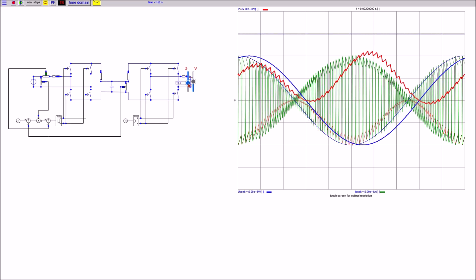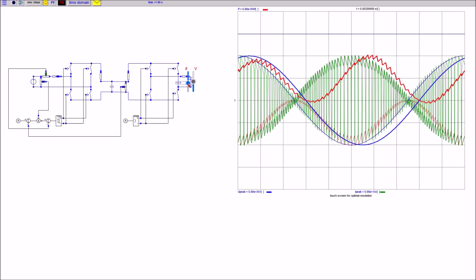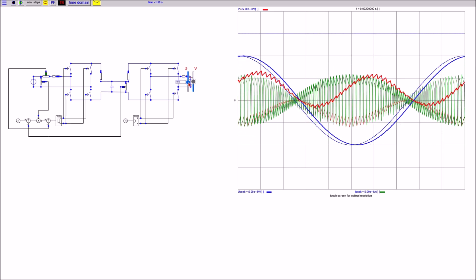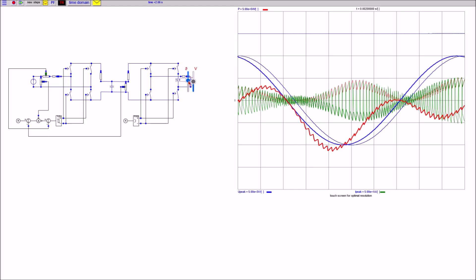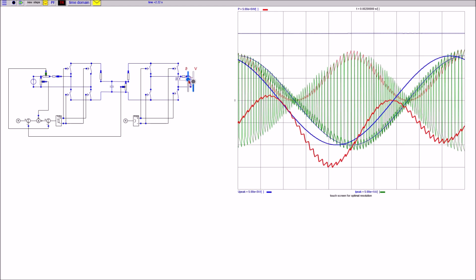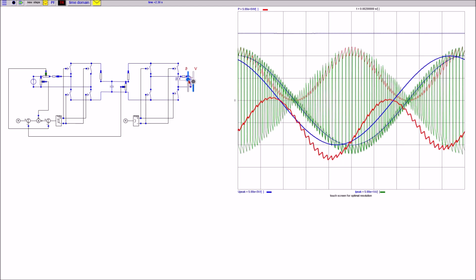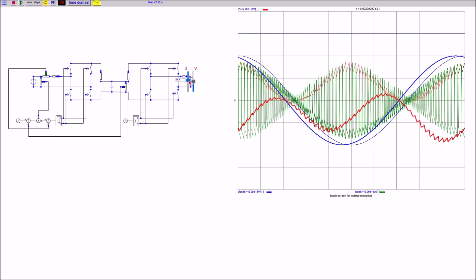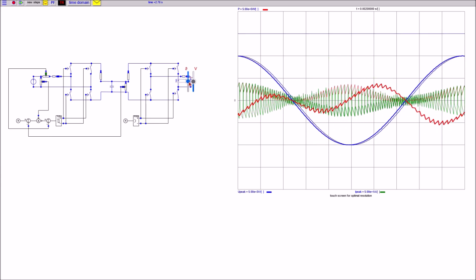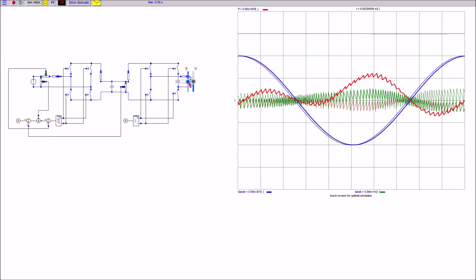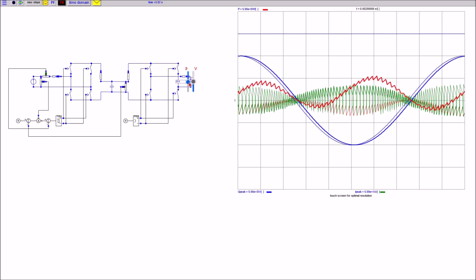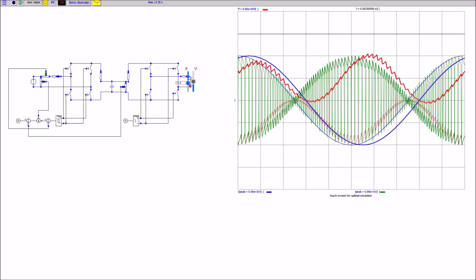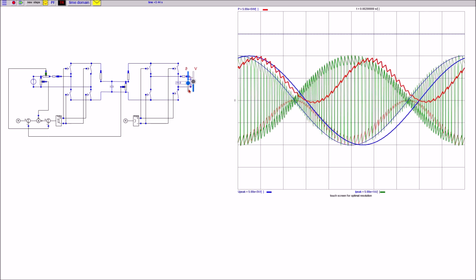Pushing power from the AC to the DC side on the right will increase the voltage on the DC side; pulling power from the DC side to the AC side will reduce it. Assuming a grid connection, a lack of power in the grid on the right side will slow down the frequency and thus increase the phase angle. As a result, power will automatically flow from the DC side to the AC grid on the right side.